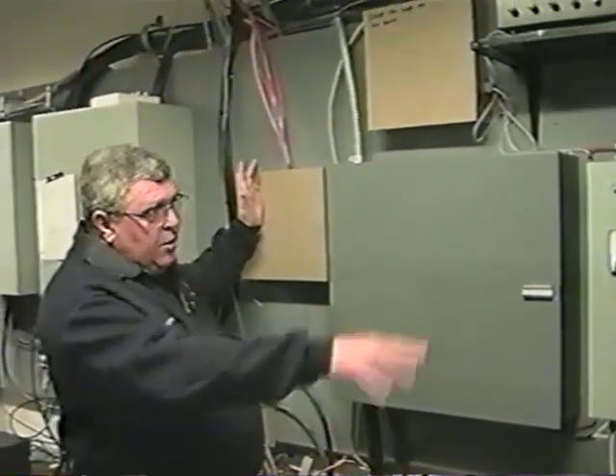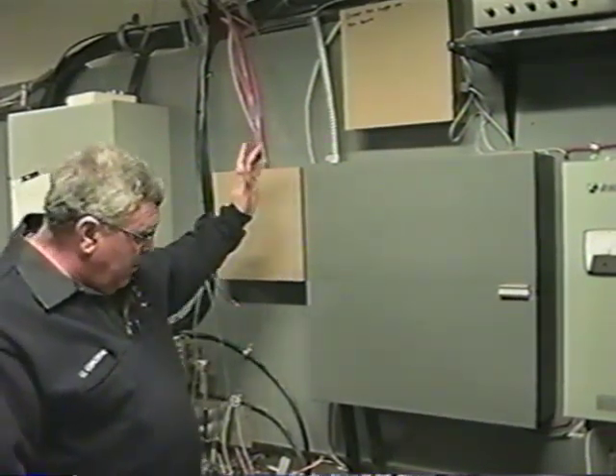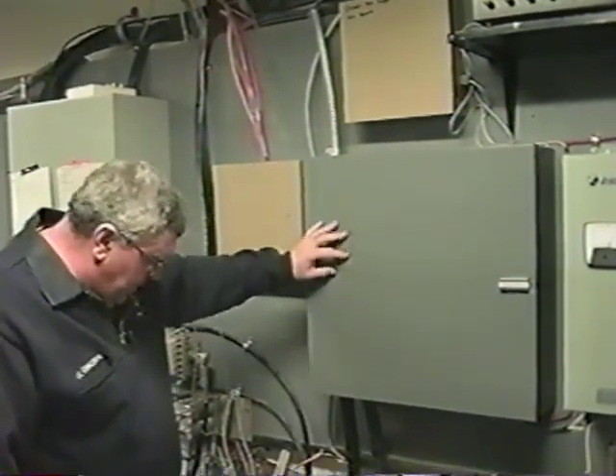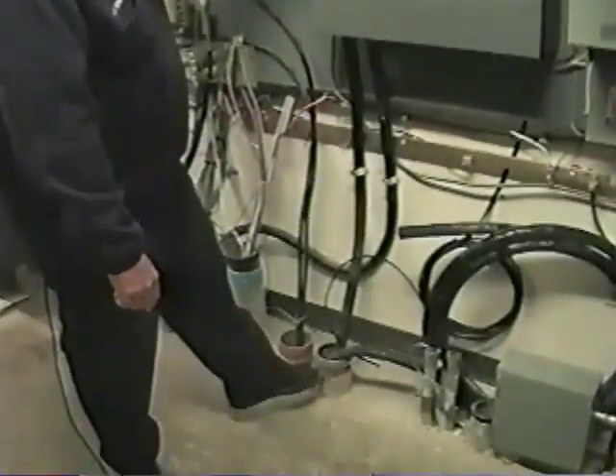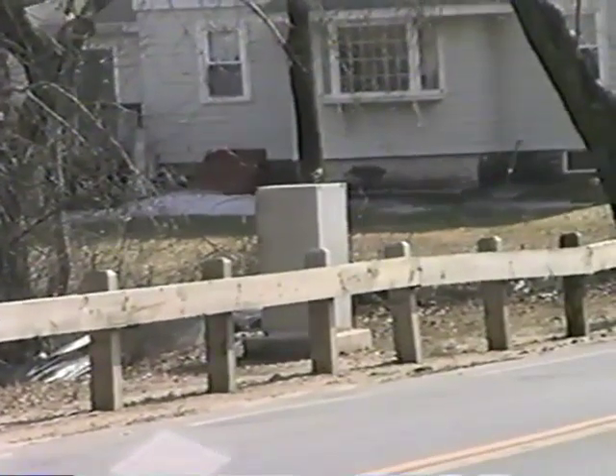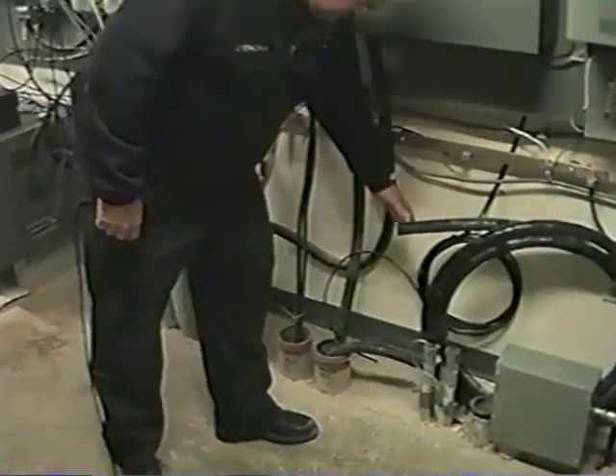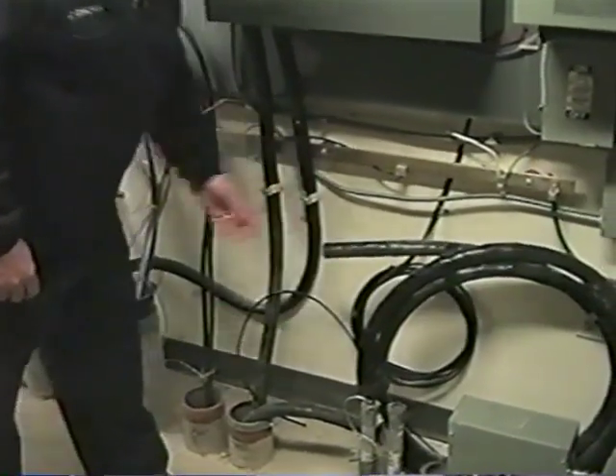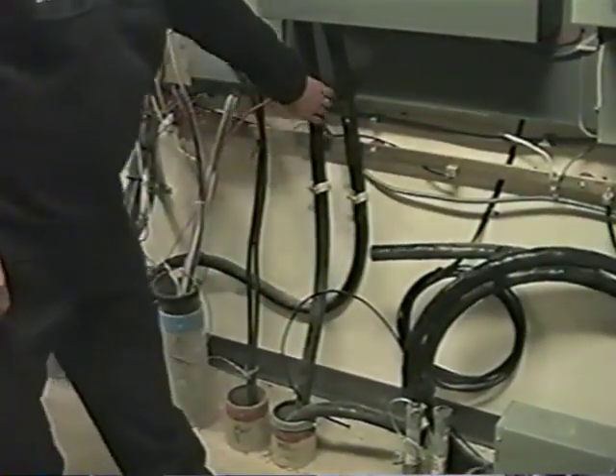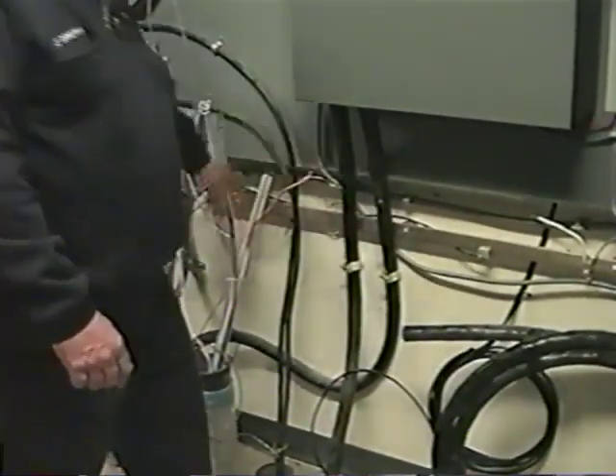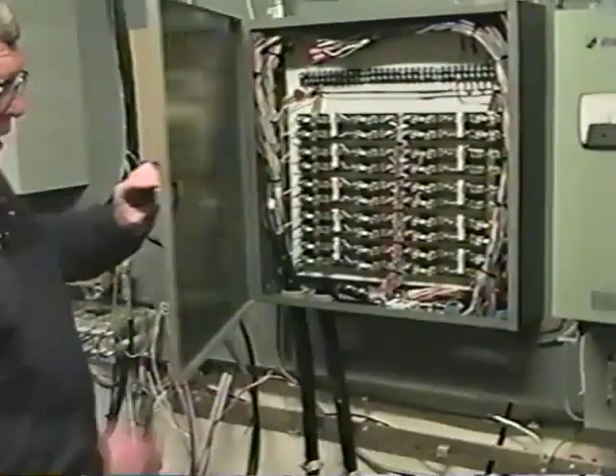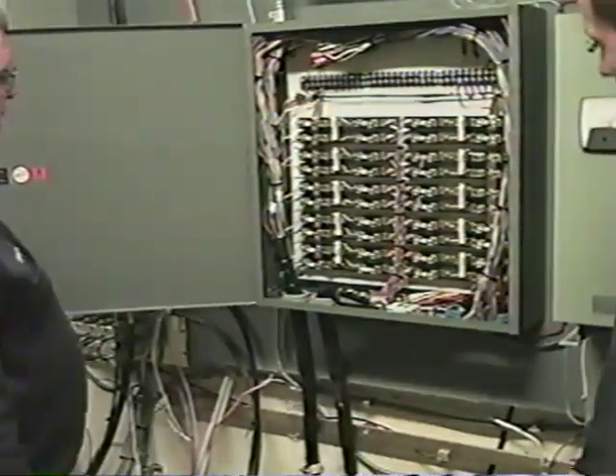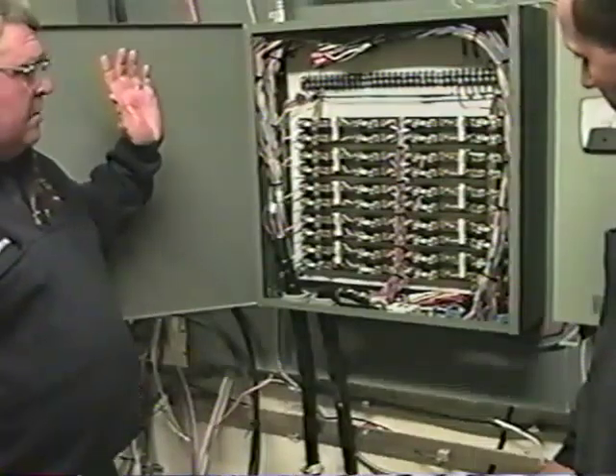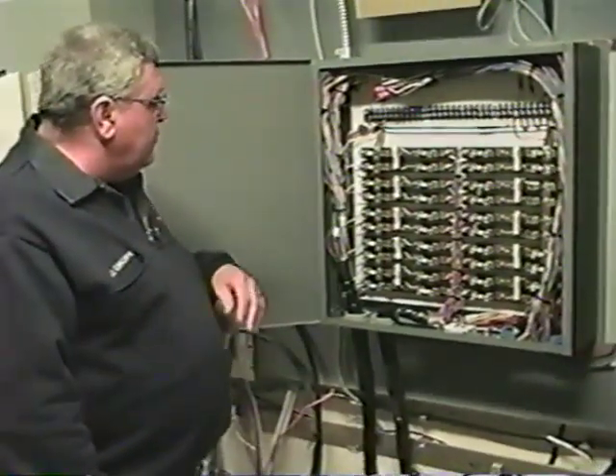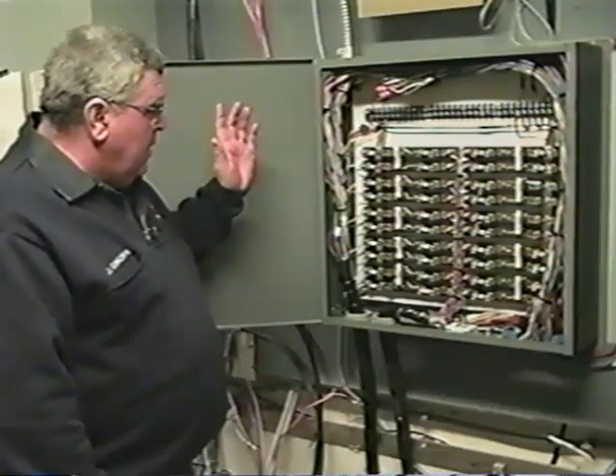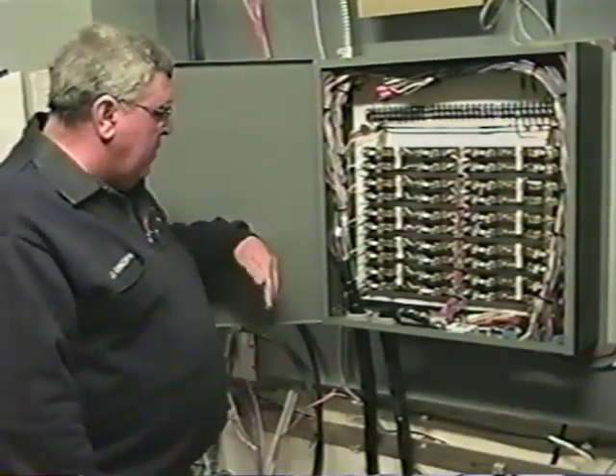This section from here to the corner behind David is all the fire alarm system. It comes in on these wires that come up through these pipes that run out into the street, into the cabinet that's across the street. It's a 25 pair wire. One comes in from the street, which is this wire here, and this other wire goes out and goes into dispatch. One big problem that any fire alarm system has, you can talk to anybody in any of the neighboring towns: thunderstorms, lightning, erroneous electrical hits from car accidents, and high voltage wire falling down on top of our wire.